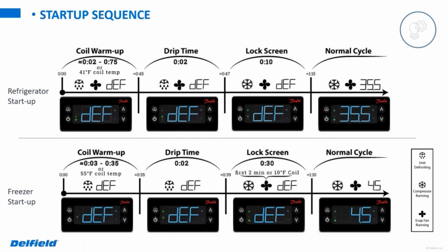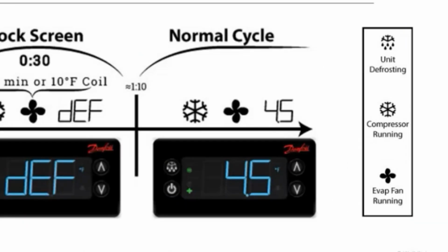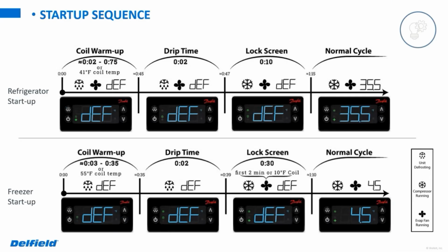So the biggest thing to take away from any of this is always look at those green icons on the side of the display. They are going to tell you what the control is actually functioning, what it's calling for. The temperature on the display, even while it is showing that temperature, only updates once a minute. So again, focus on those icons and use an independent thermometer. That will be a way to verify whether or not that display is accurate.